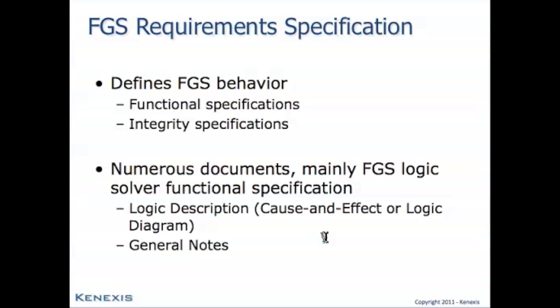In addition to the logic diagrams, the cause and effect diagrams, you may also need general notes. First off, there's going to be general requirements that apply to all of the functionality in a fire and gas system, which is much more efficient to list once, and then in the detailed sections only list exceptions to the general rules. And then also there will often be requirements for general notes where there are special considerations, or the logic is too complex to simply be represented by an X in a cause and effect diagram. These are good situations to provide general notes which clarify and supplement the logic diagram.